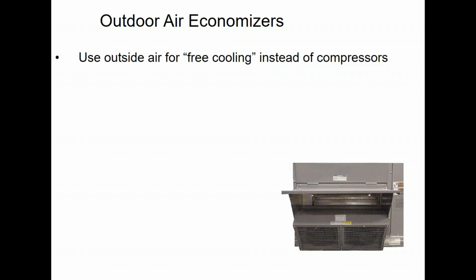So I'm not sure. When explaining economizers to consumers, to building owners, I usually explain it to them as free cooling in a way that they might relate to. So for example, at their house, if they're going to have everybody over for Thanksgiving and it starts getting hot in their house, they're probably not turning their air conditioner on. They're probably going to open up their windows. However, in a commercial building, most modern buildings don't have operable windows. And if they do have operable windows, it's not for all the rooms, it's only for the perimeter, right? So the way we handle that for the building owner is we open a window in their air handling system, in their air handler or their fan coil or their rooftop unit, something like that, to suck in that free cooling so they don't have to turn their compressor on.